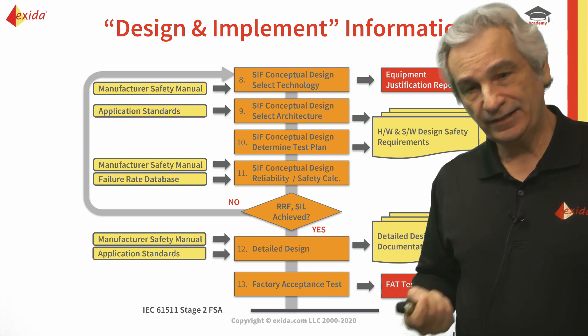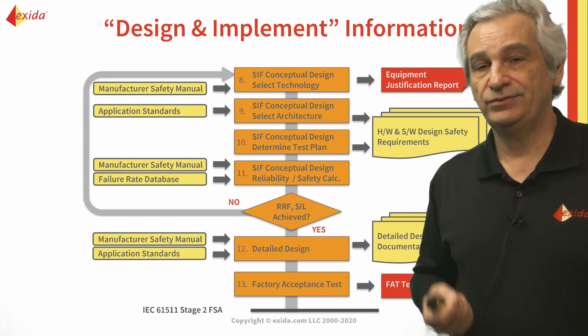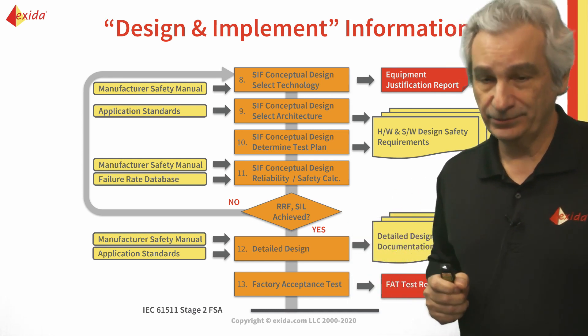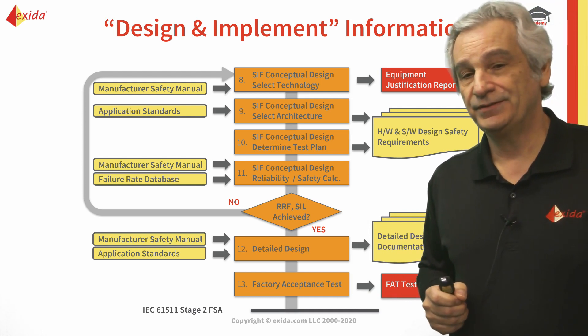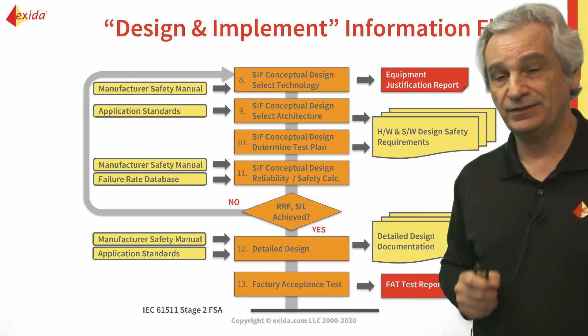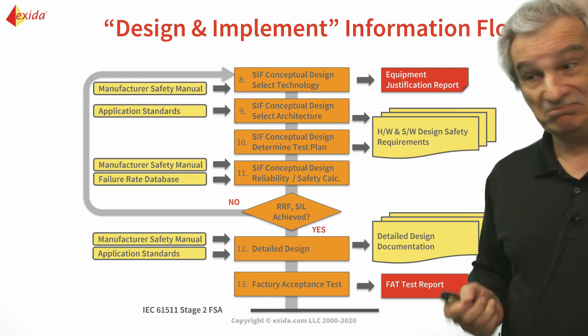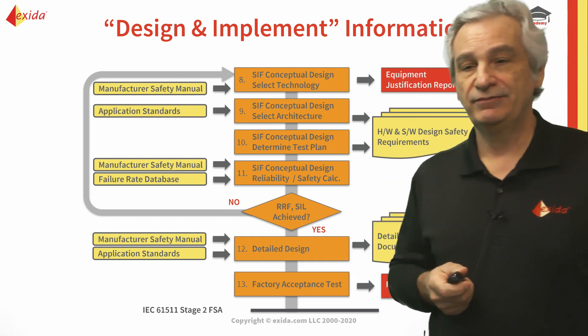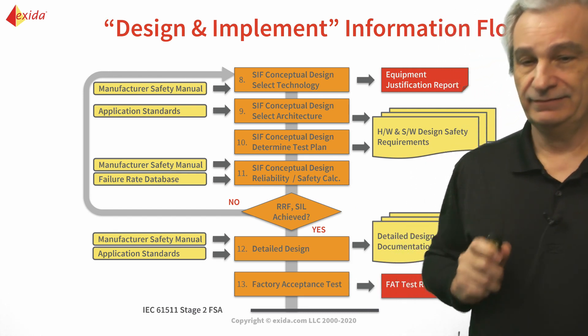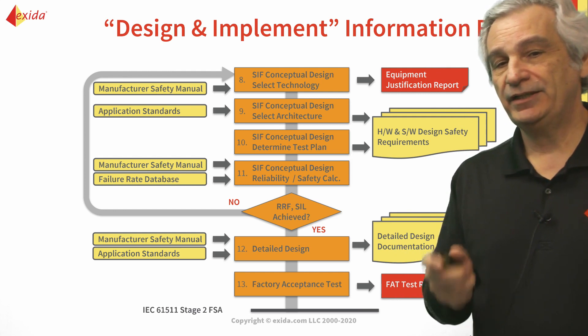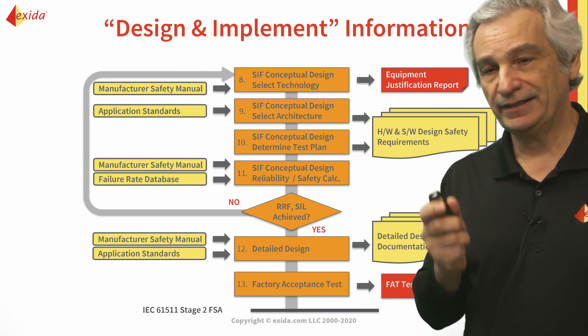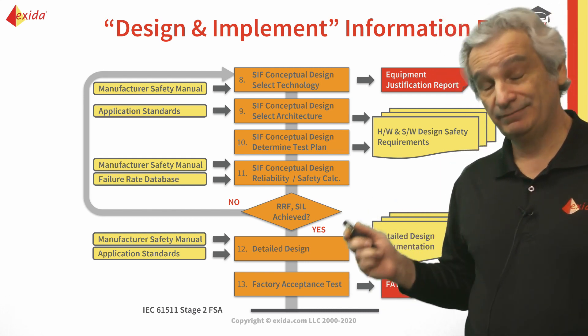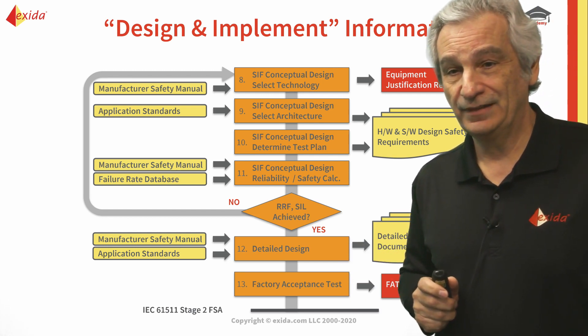The second method is through a prior use justification. When we get into that part of the course we'll go into these requirements in more detail. Those are the only two methods we can use — 'because I like the equipment' is not acceptable. We have to have a properly justifiable reason for using this equipment. We also need to make sure we think about and cover the systematic requirements, which I'll talk about a bit later on.